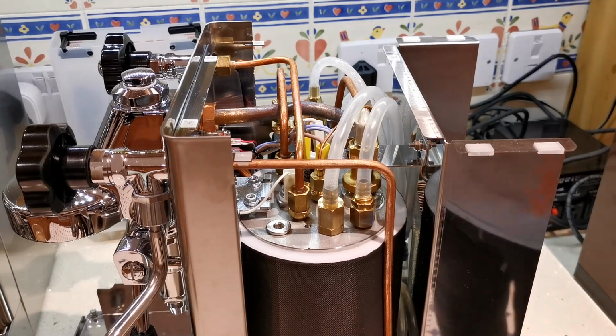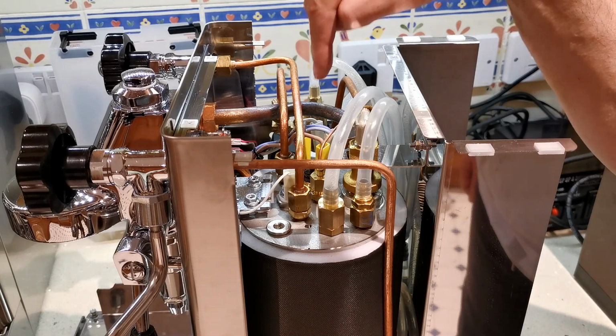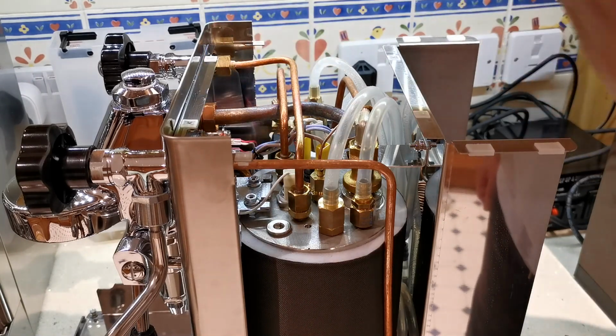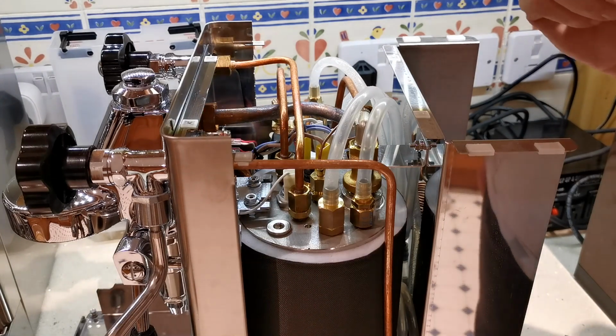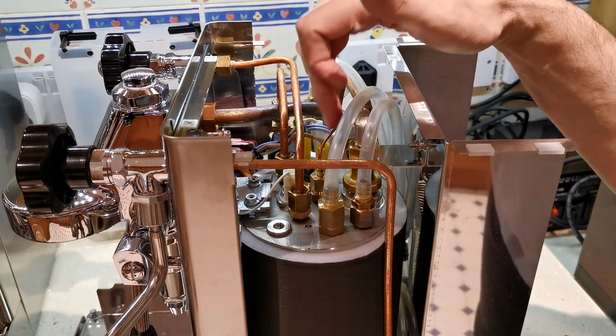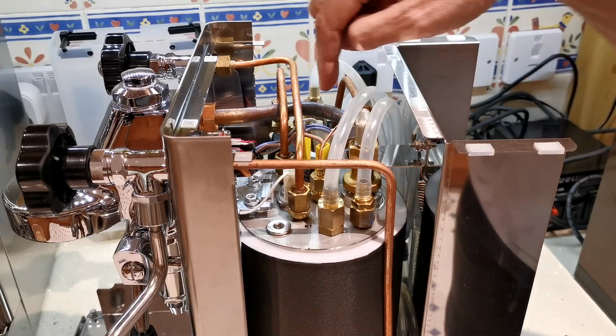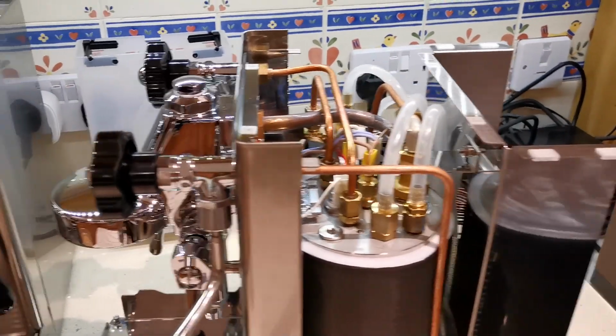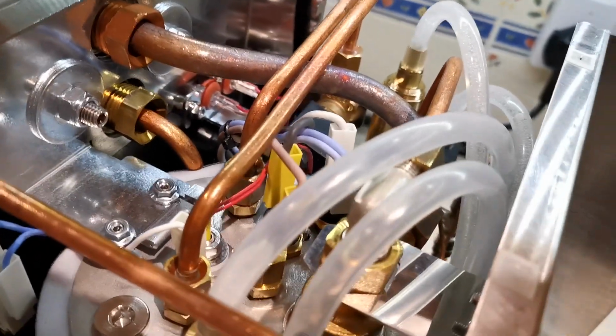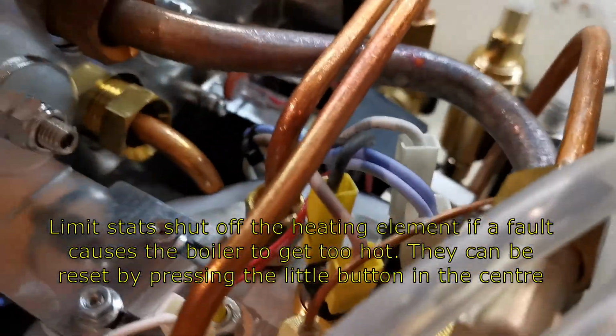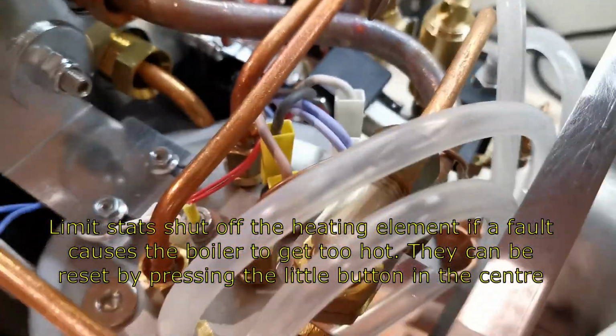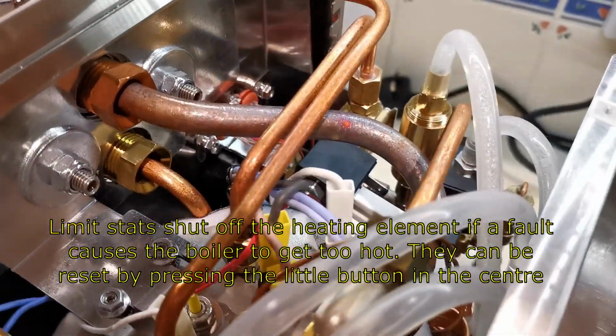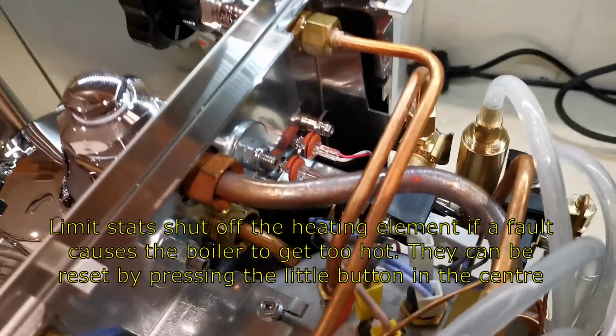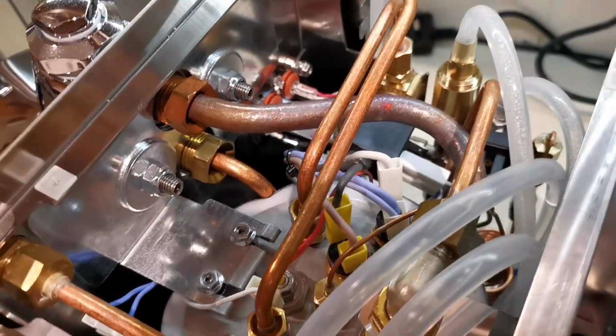That's your vacuum breaker there. Thermal sensor here. See it there? That's one of 2 thermal sensors. The other one's in the heat exchanger. You've got your pressure takeoff tube for your pressure gauge, and here and here, if you can see them, and I'm going to go in at the top again, you've got your 2 limit stats there and there. The boiler's still quite hot actually. I might use my screwdriver to point them out because there's no power to it. So you've got a limit stat there and a second limit stat there, as well as a safety valve. So you've got lots of redundancy should there be a failure of one of the components.